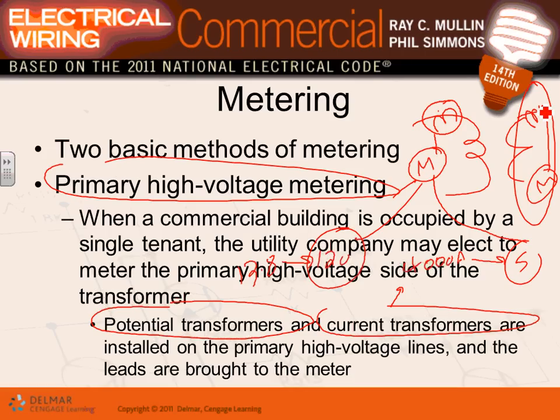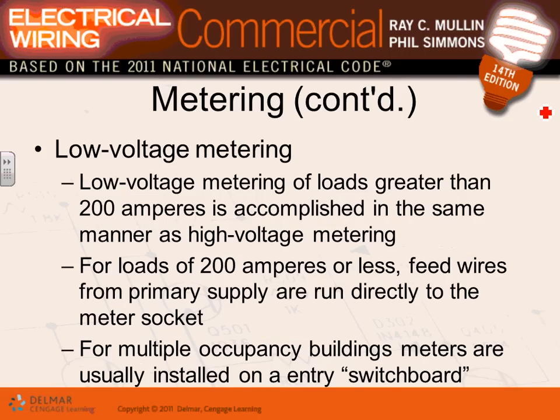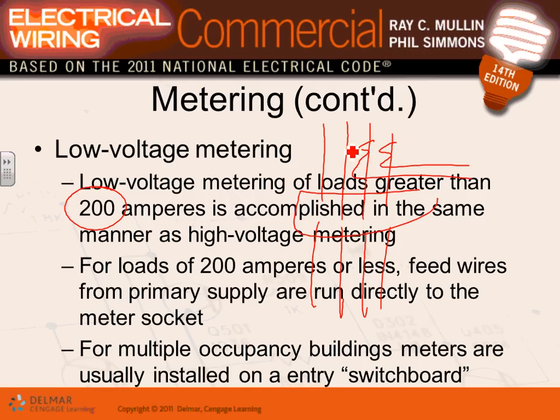So I want to refer you this one to the industrial, because in the industrial, guys, we talked about the higher voltages. Low voltage metering is what we do, guys. Let's focus on the low voltage. On the low voltage side, typically up to 200 amps, you can bring hot 1, 2, 3, and a neutral to the meter, 1, 2, 3 out of the meter. If it's larger than 200 amp, they have CTs. Here's what they do: CTs, current transformers, to a meter. The meter will be sitting here instead of the meter being here. So they don't bring the cables into the meter.